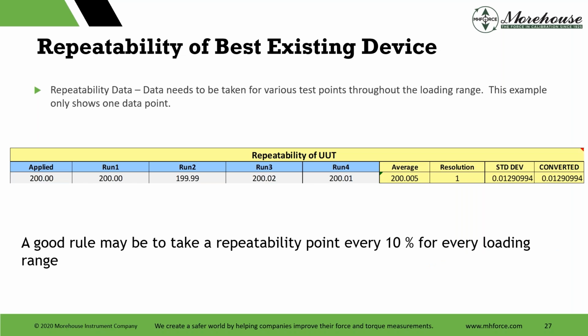So that repeatability data that I showed you that was the largest needs to be taken for various test points throughout the loading range. This example only shows 1 point and 4 points. Maybe that number is larger, and if we want to get that down, maybe we need to take more measurements. Maybe we need to take 5, 6, 7. A general good rule for any load cell I'm going to use as a reference standard would be to take a repeatability point every 10% for the loading range.